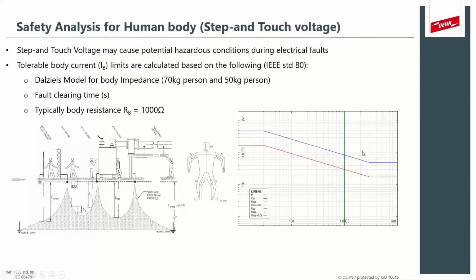Now, this is critical because with lightning, we talk about the microsecond range. As you remember, the 10 by 350 microsecond waveform. So the graph will be moved up way further back here, and the voltage limit will actually be very high as compared to power frequency simulations. Now, in this specific case, just to keep in mind, we're talking about a step voltage limit of 841 volts. This limit is important for the example that we're going to do in subsequent slides and sections.